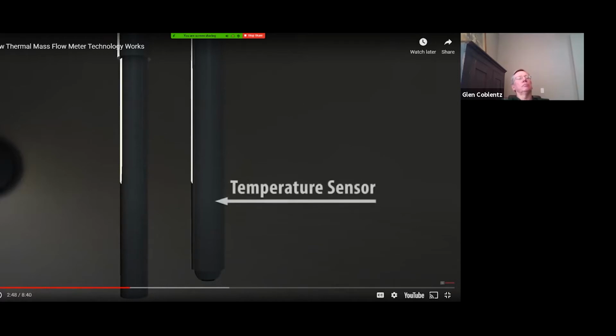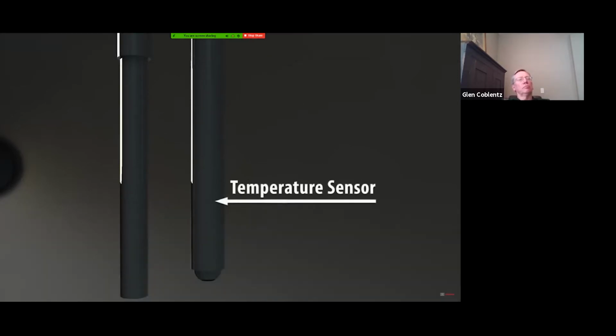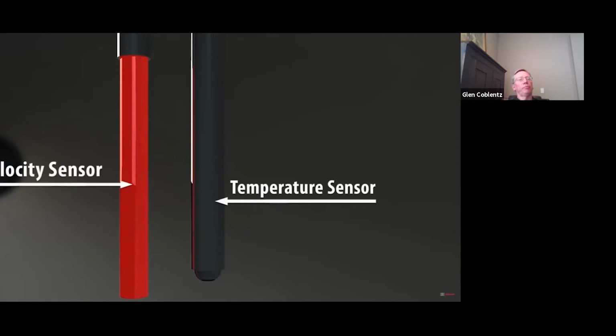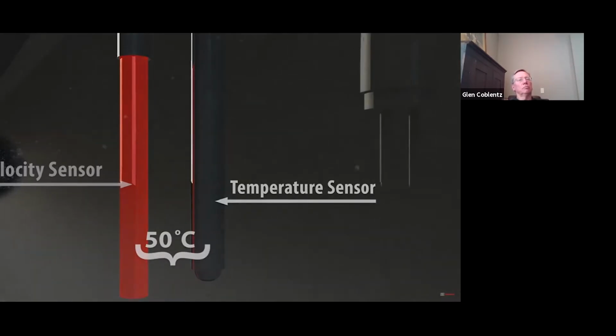Thermal flow meters have two sensors immersed into the flow stream. One is a temperature sensor, which measures the actual gas temperature inside the pipe as a reference, regardless of the flow velocity. The other is a heated sensor called the velocity sensor, illustrated here in red. As the name implies, thermal dispersion mass flow meters use heat to measure flow. The velocity sensor is heated continuously via electrical wattage so that a predefined temperature differential is always maintained between the two sensors. For example, 50 degrees Celsius is the constant temperature differential for Sierra meters.